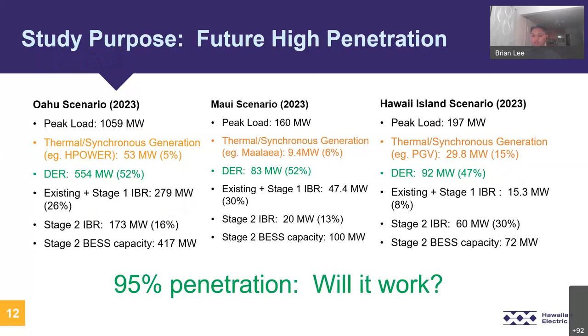A few important points to mention: the total synchronous generation for all islands in orange ranges from 5 to 15%. Total DER generation is about 50% of the load, and centralized IBR projects fill the remaining gaps for generation. The existing and stage one IBR projects are in grid following mode, and the stage two projects were studied in their grid following and grid forming implementations of their plant. So in total, we have about 95% IBR penetration, and the purpose was to study: will this work?